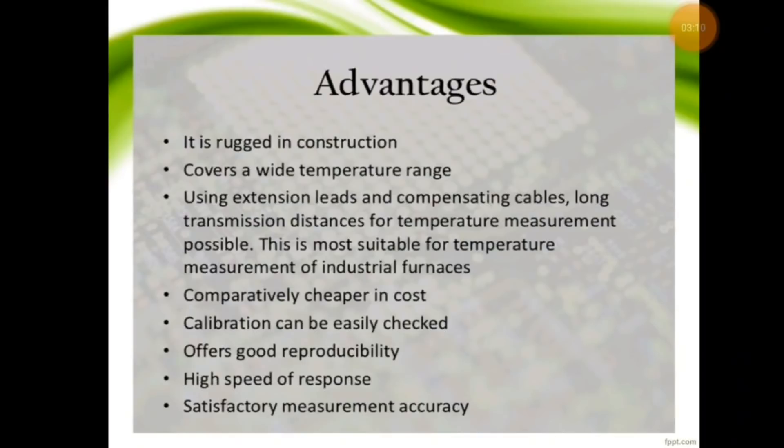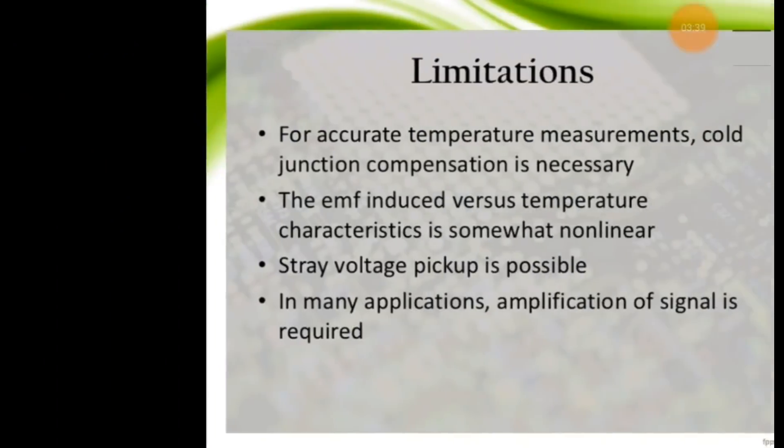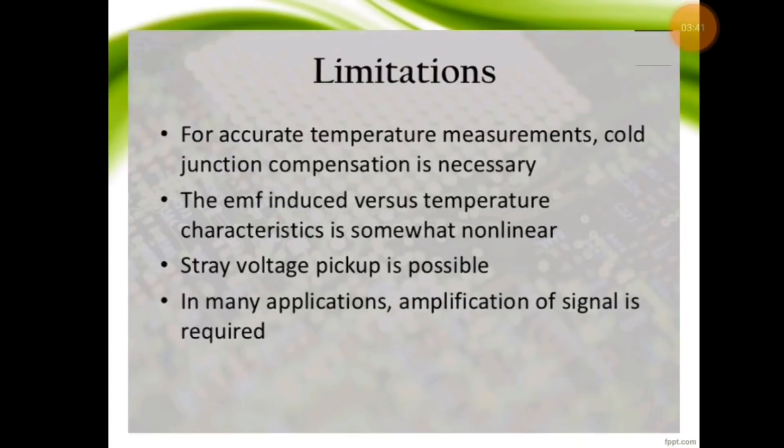Advantages: it is rugged in construction, covers a wide temperature range, using extension leads and compensating cables allows long transmission distances for temperature measurement, most suitable for industrial furnaces, comparatively cheaper in cost, calibration can be easily checked, offers good reproducibility, high speed of response, and satisfactory measurement accuracy.